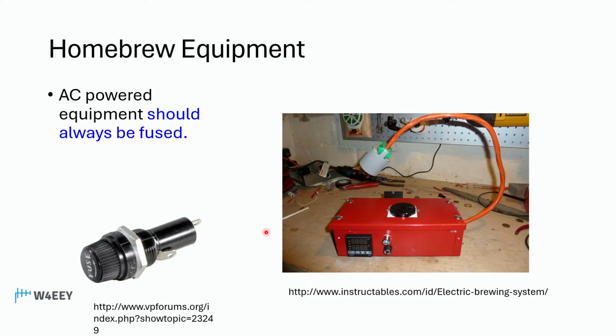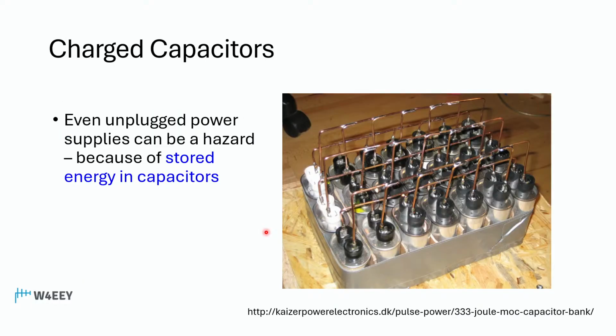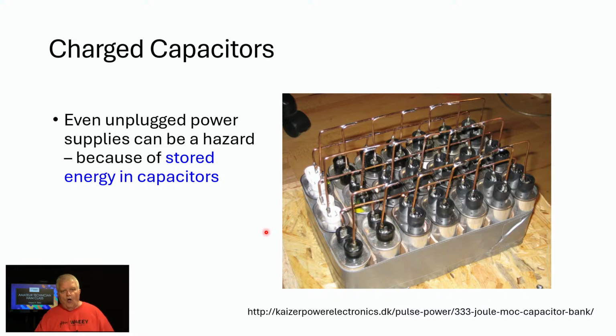And if you are working on equipment, always be mindful that capacitors may retain an electrical charge even if the power is removed. A lot of amplifiers, for example, have circuits that are designed to bleed off energy from capacitors inside the amplifiers. But sometimes those circuits can fail. So you always want to make sure that if you're working on an energized device that has large capacitors in it, you might want to remove the power from the device and then even short out the capacitors with a grounding stick to eliminate that stored energy in the capacitors.